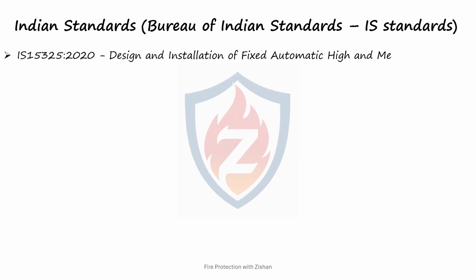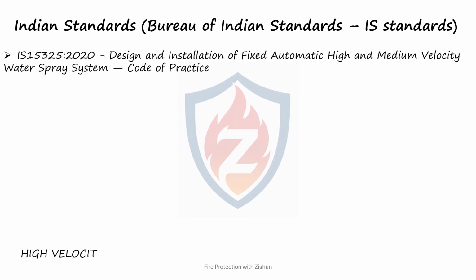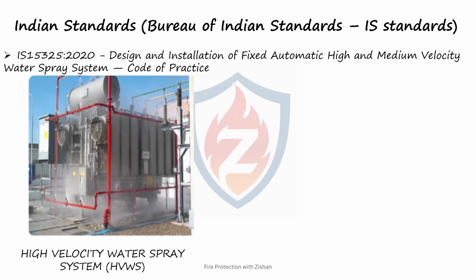These specialized fire protection systems are commonly used to protect high-hazard equipment such as transformers, cable galleries, oil storage tanks, and other industrial installations where rapid fire control is essential. On the left, we can see a high-velocity water spray system, or HVWS. This system uses specially designed high-velocity nozzles to discharge water at high speed and in a concentrated pattern. The primary purpose of HVWS is to extinguish fires involving flammable liquids and protect critical equipment such as oil-filled transformers by quickly cooling surfaces and suppressing flames.